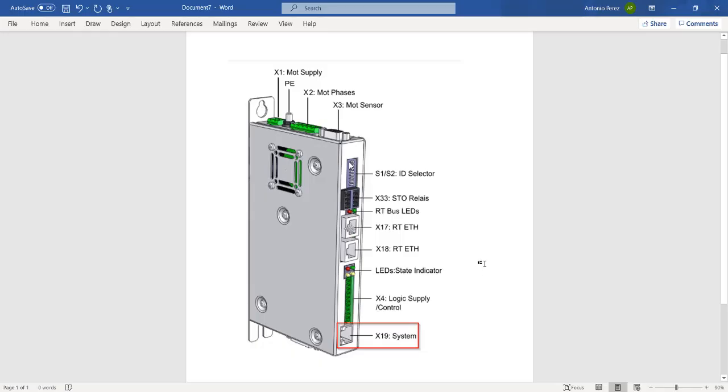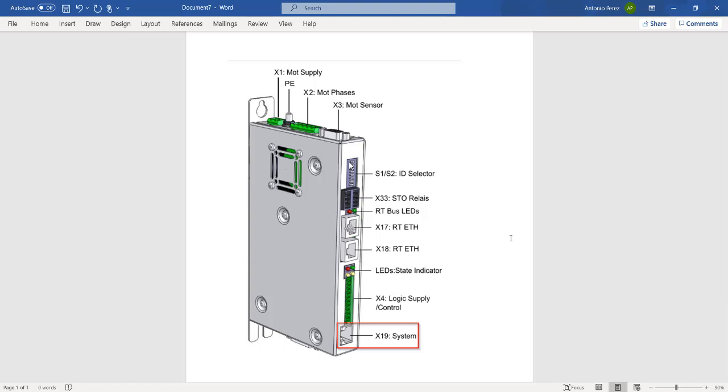The drive that we are using today is the C1250 drive. On the drive, we have three RJ45 ports: the X17, X18, and X19. The X17 and X18 real-time Ethernet ports vary depending on the communication protocol defined for the drive type. The X19 port will be for RS-232 serial communication using the RJ45 connector across all C1250 drives.